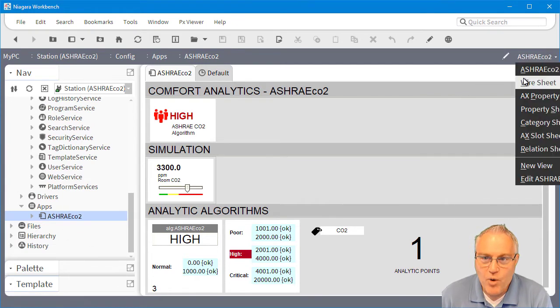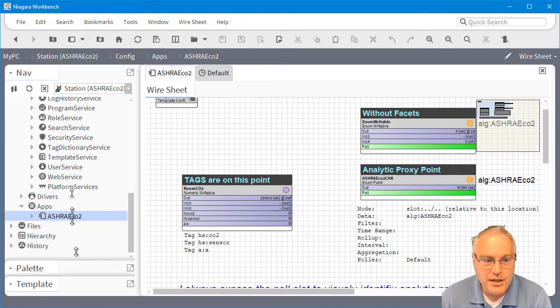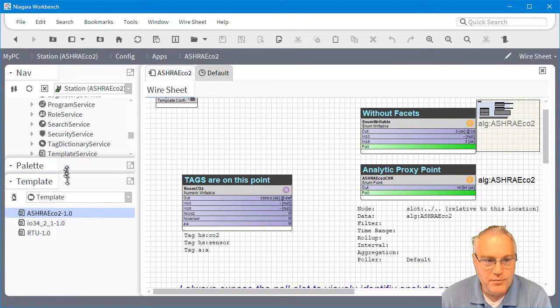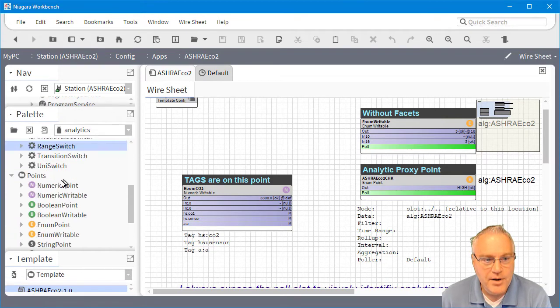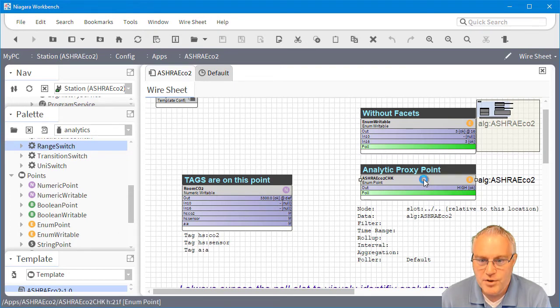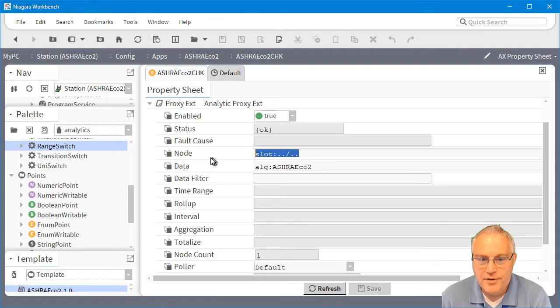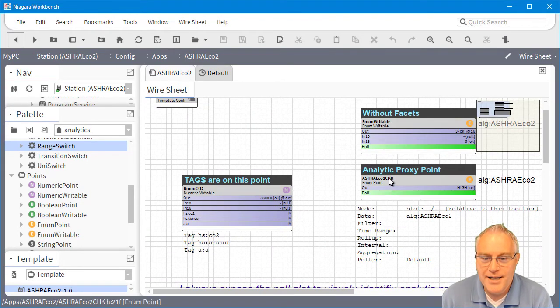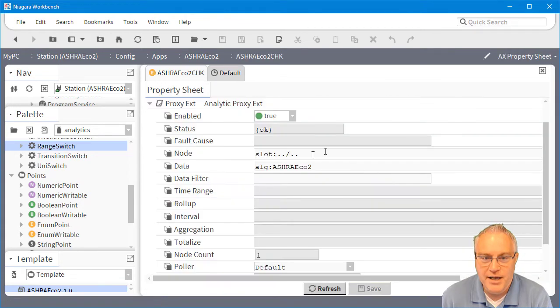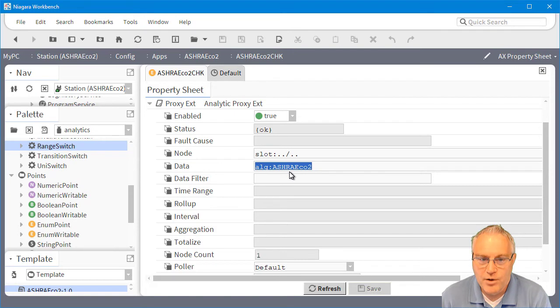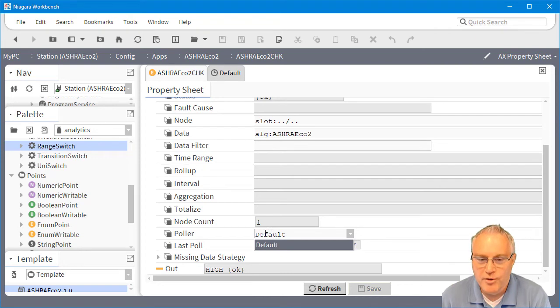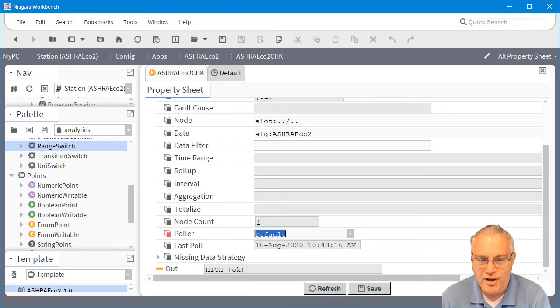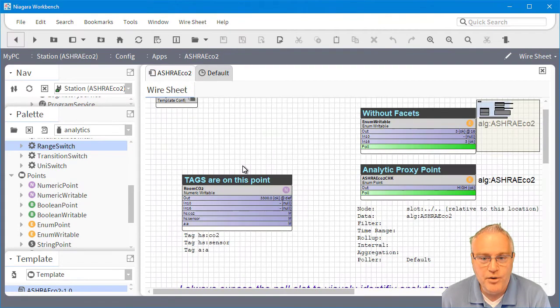If we look at the wire sheet now, all I had to do was put in an analytic proxy point. If you go to the analytics palette under the points, I can drag out an enumerated writable. I did that for the main algorithm. I left the default which is relative to where it's at. The point I'm going after is right here, right on the same wire sheet. I didn't have to point to anything. I just say look at that same level, execute the algorithm. This was the default poller from the other station, so I just had to select it. I chose the only poller available which was default. Then I said save, so now that's ready to go.